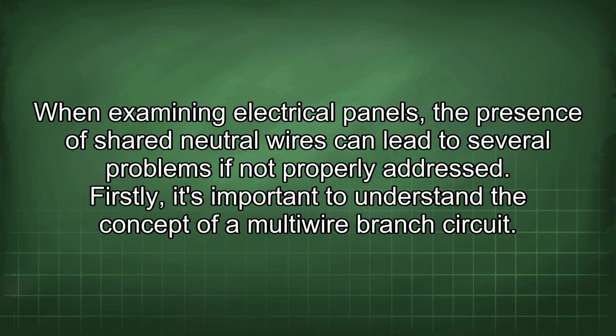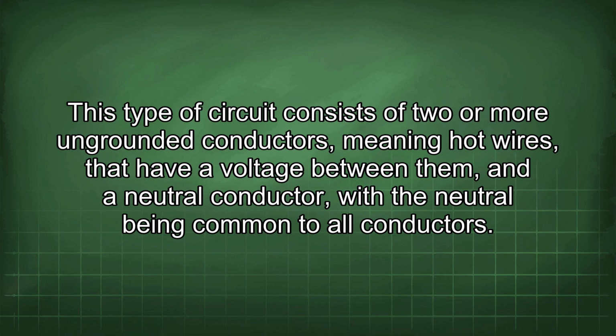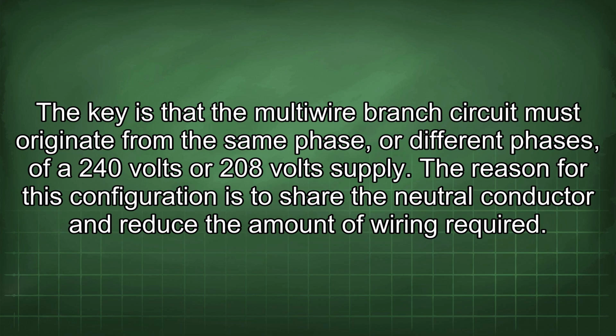When examining electrical panels, the presence of shared neutral wires can lead to several problems if not properly addressed. Firstly, it's important to understand the concept of a multi-wire branch circuit. This type of circuit consists of two or more ungrounded conductors, meaning hot wires, that have a voltage between them, and a neutral conductor, with the neutral being common to all conductors. The key is that the multi-wire branch circuit must originate from different phases of a 240 volt or 208 volt supply. The reason for this configuration is to share the neutral conductor and reduce the amount of wiring required.